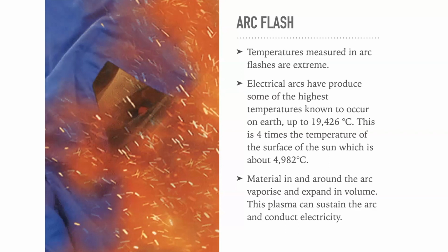That arc reaches temperatures up to 4 times the temperature of the surface of the sun. Look at that, this is straight off Wikipedia. So nearly 20,000 degrees Celsius, but it's very focused. So the temperatures of arcs are very, very high. How far they extend is based on a calculation, which we'll look at in a minute.